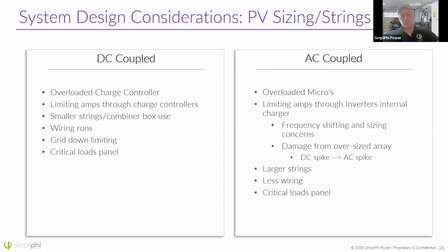Now, one thing to understand though is sizing is much more critical with an AC coupled system. So with a DC coupled system, you're worried about open circuit voltage and short circuit current. With an AC coupled system, you're worried more about sizing. So you're looking at this microinverter's specs and it says I can only handle 310 watts, but you can overload me as much as 50%, for example. So understanding how far you can overload these microinverters is important.